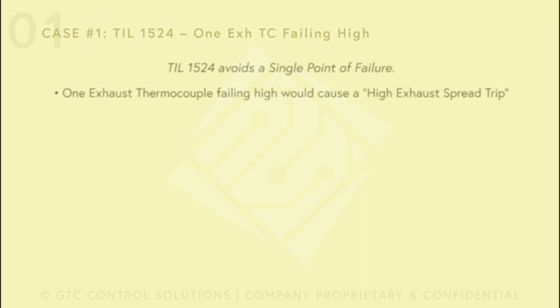So the recommendation is, if one thermocouple fails high in operation and you have this TIL implemented already, disconnect that high exhaust thermocouple, the one that has failed high, and then you still have a better chance of limping out to the next outage and doing the exchange of the thermocouple, if the thermocouple cannot be exchanged online.